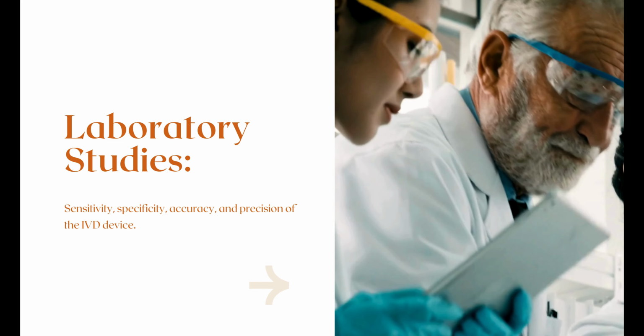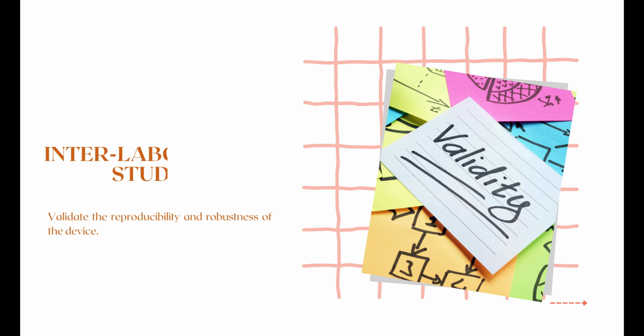Seventh, from analytical and performance studies, where from the laboratory studies, data from analytical performance studies conducted in laboratories to evaluate the sensitivity, specificity, accuracy and precision of the IVD device is collected. Laboratory studies to validate the reproducibility and robustness of the device are also collected.